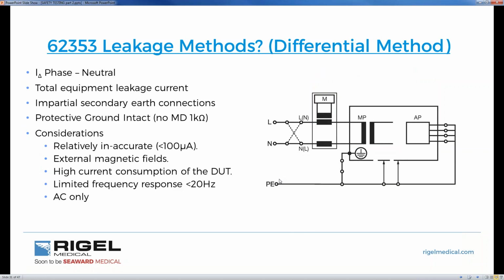Differential method. The differential method is not susceptible to secondary earth, and it measures the total leakage of a system, because we're not measuring through the 1K body model. Every other test that measures leakage, 60601, 62353, we're always measuring through a 1K body model. So 1K will be in series of the circuit. If 1K is in series all this time when measuring, just like any current shunt, it's not the true leakage measurement. There's impedance there. Something to consider when you think about measuring leakage current.